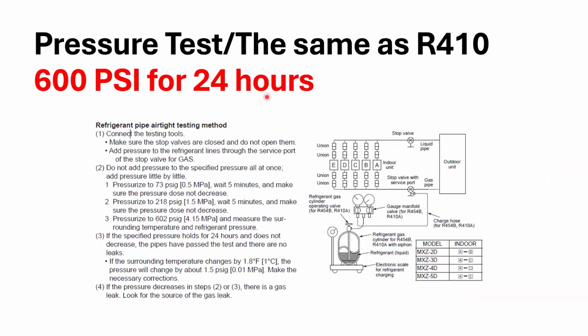And then back to pressure testing, it's the same as R410. And 600 PSI for 24 hours has always been our requirement. And again, this is just out of the service manual right here, breaking it down and going through exactly what they're saying out of the manual to give you an idea what they're saying.